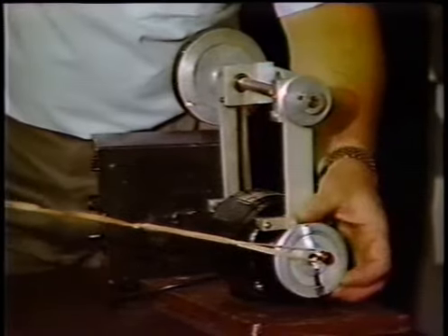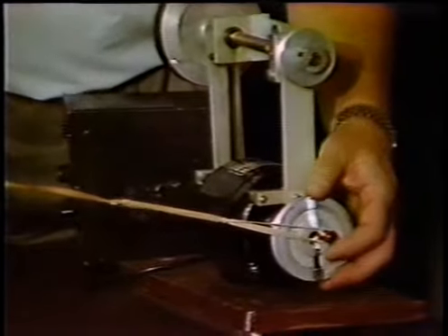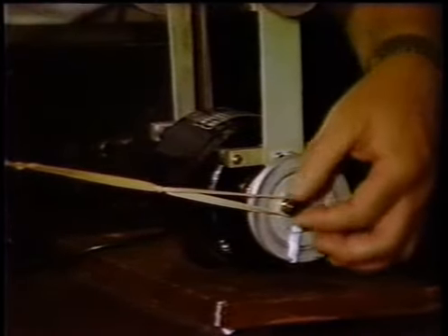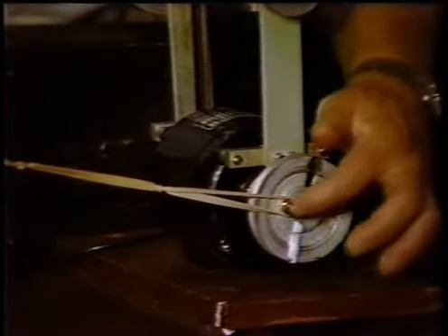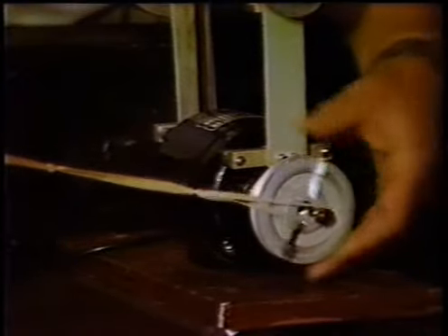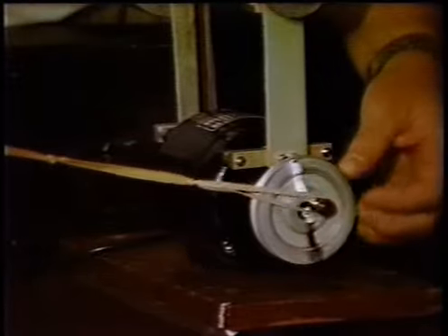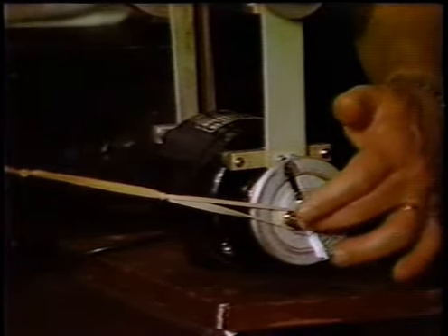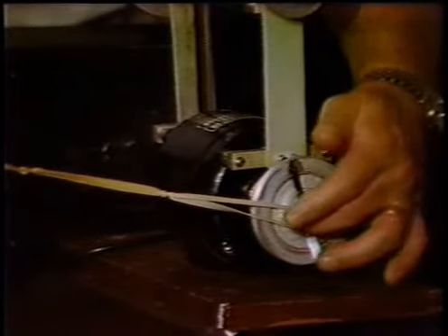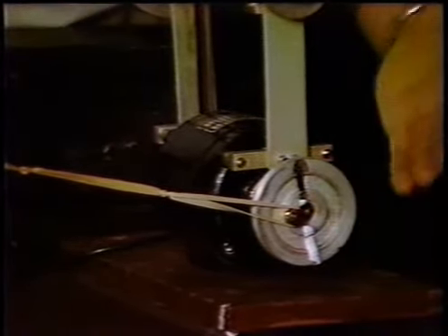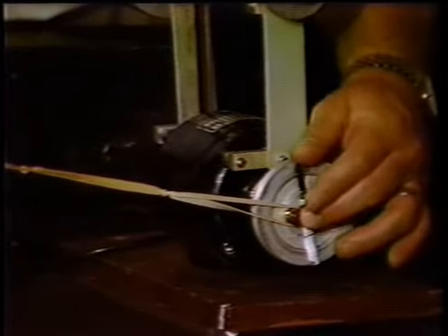What we have here is a variable speed motor. It's a DC SCR drive motor. And to create an exciting force, what we've done here is simply drilled and tapped a screw off-center, or eccentric, so that as this rotates, it produces a 1 times RPM excitation. Now, I want you to notice that the amount of eccentricity here is approximately 1/2 inch, giving us a total peak-to-peak eccentricity, exciting force, if you will, of approximately 1 inch.